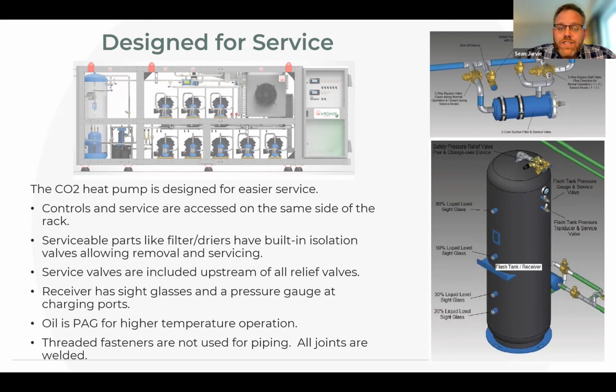All parts are serviceable. And a lot of times these are mission critical loads, especially in heating modes, where they can't go down. You can't turn off your heat in the middle of winter to do some basic maintenance and service. So all the critical components have isolation around them so that you can turn it off, service it, and put it back into service without shutting the primary system down. So as long as you're doing preventative maintenance type items, the system can 100% stay running.